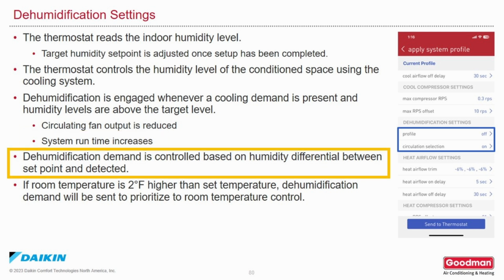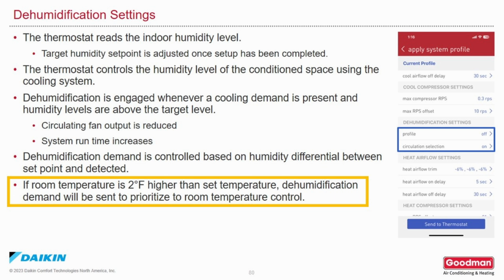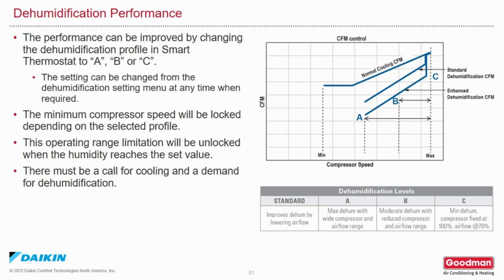Dehumidification demand is controlled based on the humidity differential between set point and the detected humidity. If the room temperature is 2 degrees Fahrenheit higher than the set temperature, dehumidification demand will be set to prioritize room temperature control. After you've set your dehumidification settings, the dehumidification performance can be improved by changing the dehumidification profile in the smart thermostat to A, B, or C. Settings for these profiles can be found in the IOM. The settings can be changed from the dehumidification setting menu at any time when it's required.